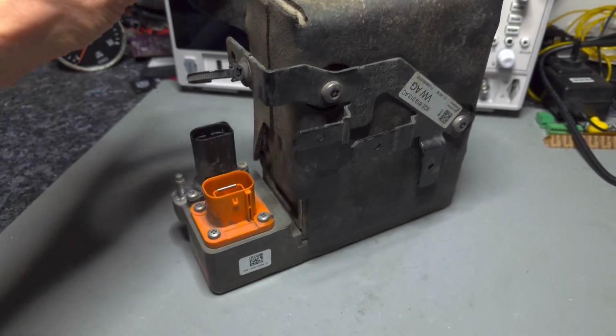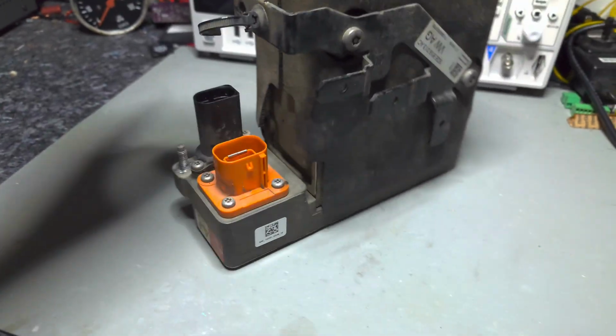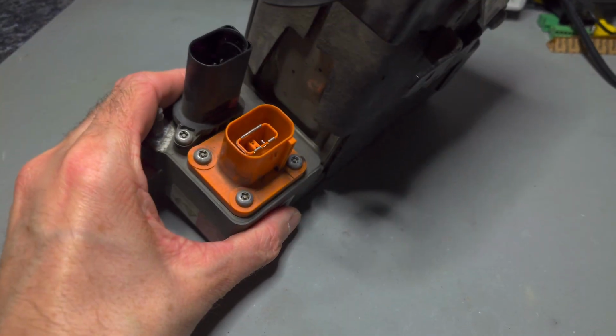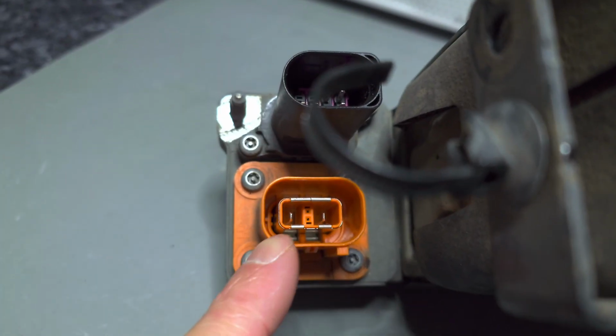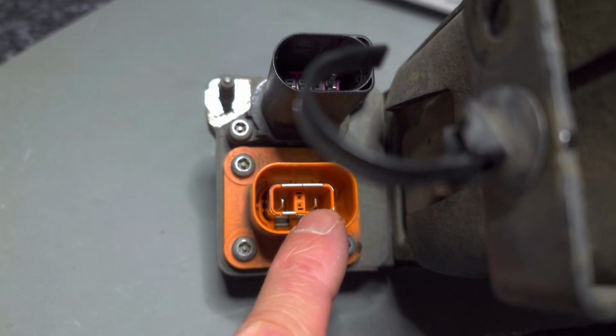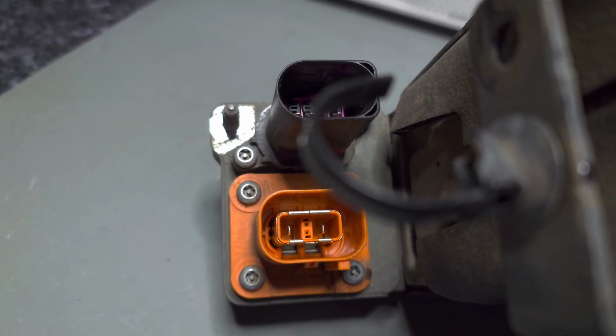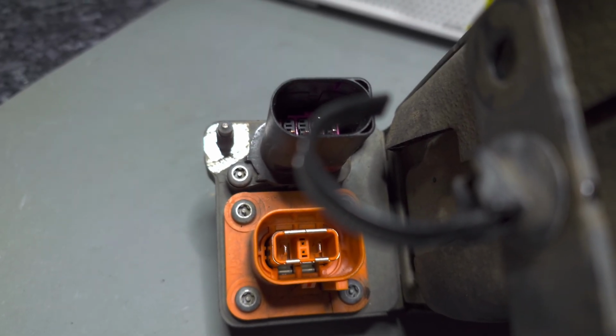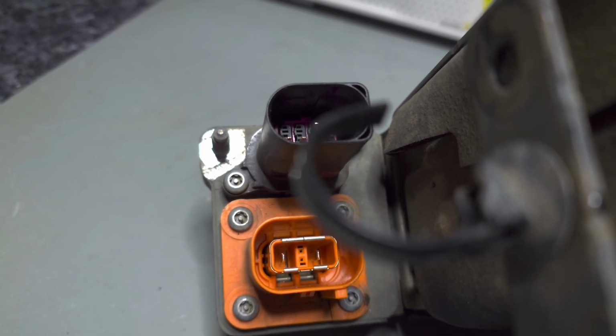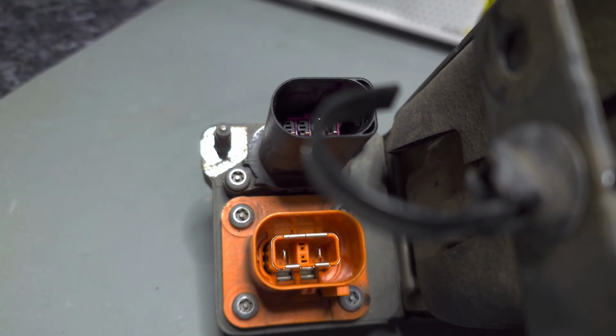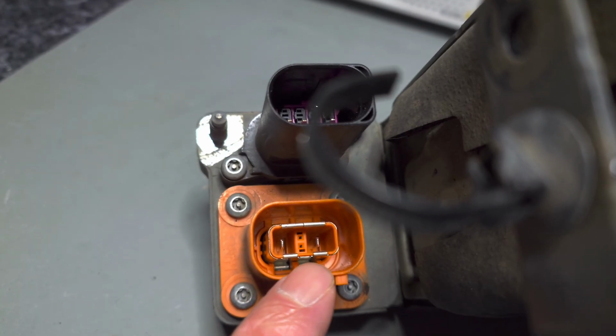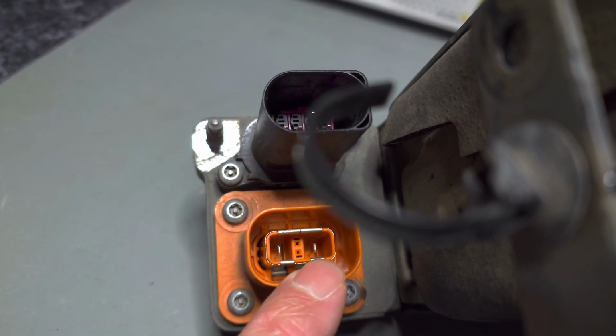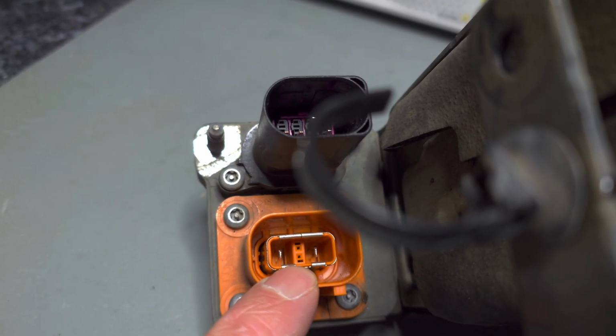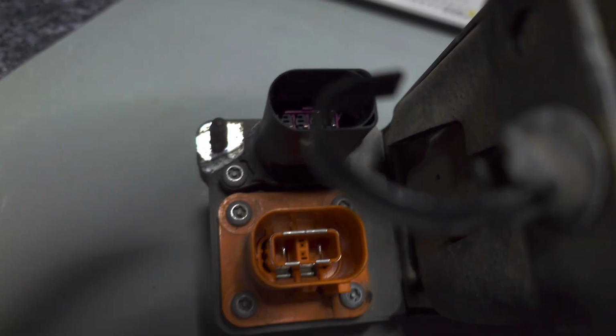Well, that's quite simple. If you use a multimeter set to ohms or resistance, and run it across these two metal pins, on a working unit with an open circuit you should see about 1.4 mega ohms in one direction. If you change polarity, the meter couldn't measure anything - open circuit. If, like this one, it's failed to some extent, you'll see a fairly low resistance across here - in this case about 90 ohms, which is equivalent to about 1.5 kilowatts.